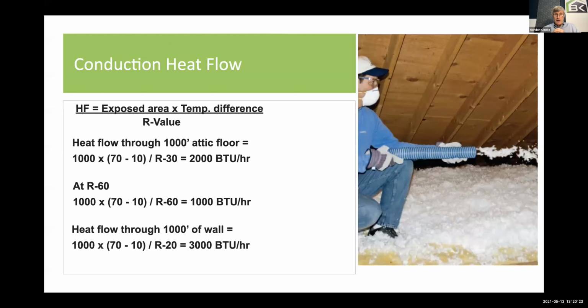And if I went to the wall, for example, R20, now of course I have 3,000 BTUs because I have less insulation. Now you're immediately going to ask, well, wait a minute, is that R20 real or is the R20 effective R value? And it's a good point. The early days of heat loss, heat gains, they just took nominal insulation values, the insulation value in the stud space itself. They didn't necessarily consider the studs. The newest and best heat loss, heat gain software would actually ask you to build the wall. They would ask you what the stud spacings in the wall are, and it would make the calculation in the background. So you might still enter R20, but it may say yes, but I'm going to assume there are some studs in the wall, and therefore I'm going to take it down to R15, for example.